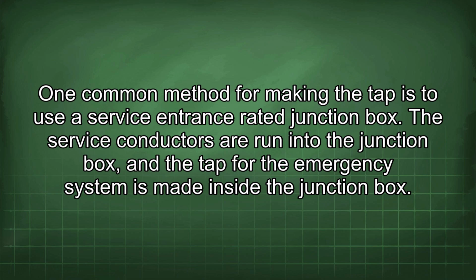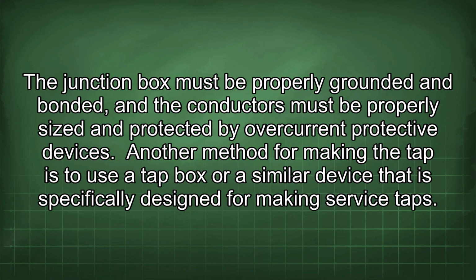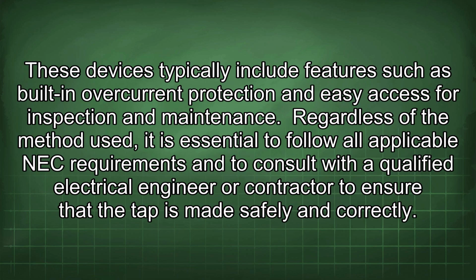One common method for making the tap is to use a service entrance rated junction box. The service conductors are run into the junction box, and the tap for the emergency system is made inside the junction box. The junction box must be properly grounded and bonded, and the conductors must be properly sized and protected by overcurrent protective devices. Another method for making the tap is to use a tap box or a similar device that is specifically designed for making service taps. These devices typically include features such as built-in overcurrent protection and easy access for inspection and maintenance.